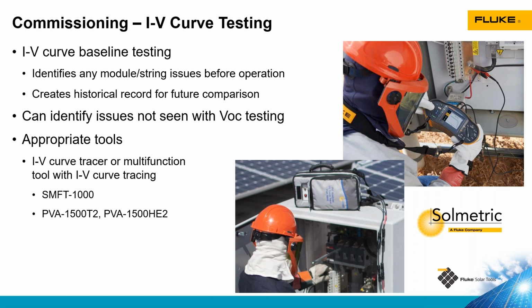The big difference between these 3 models is how they handle high efficiency modules. With that type of module, the cell has a high capacitance, and when the IV curve test starts, there's a large inrush current to the test tool. This can do a couple things. With some tools like the SMFT 1000, if the efficiency is above about 19%, they'll see that inrush current as an overload short circuit current, and they'll prevent the test from starting to prevent damage to the unit.